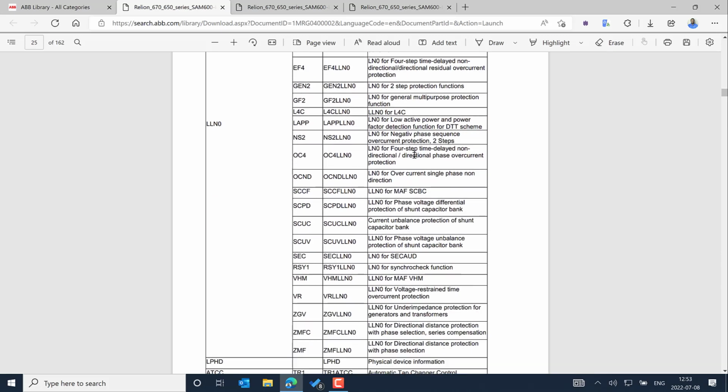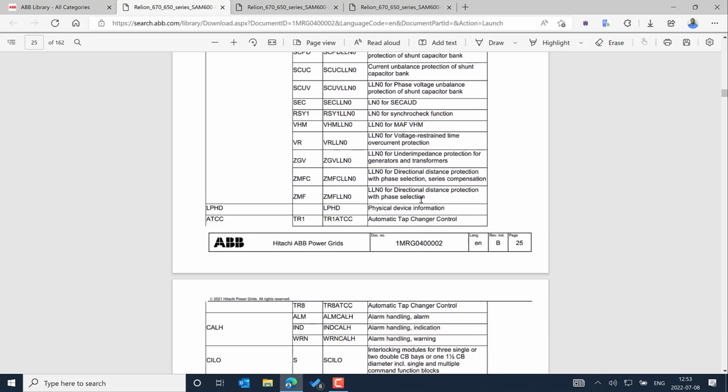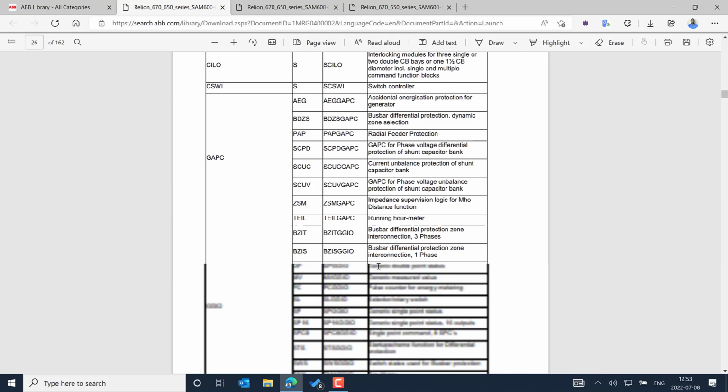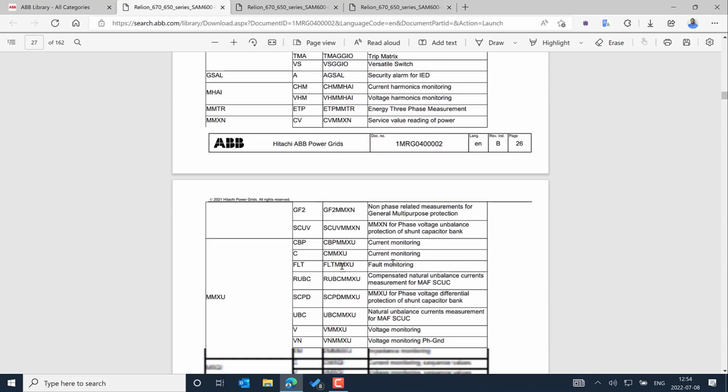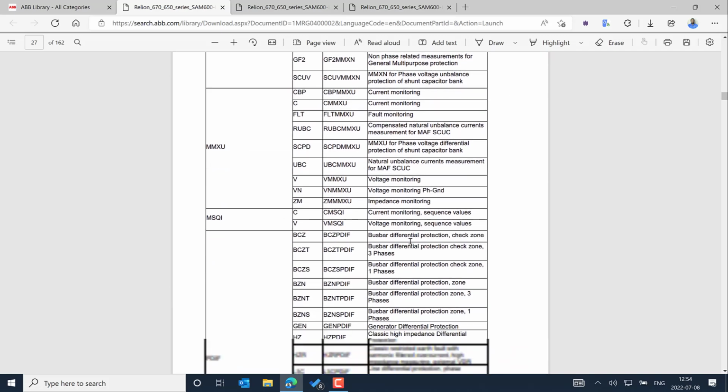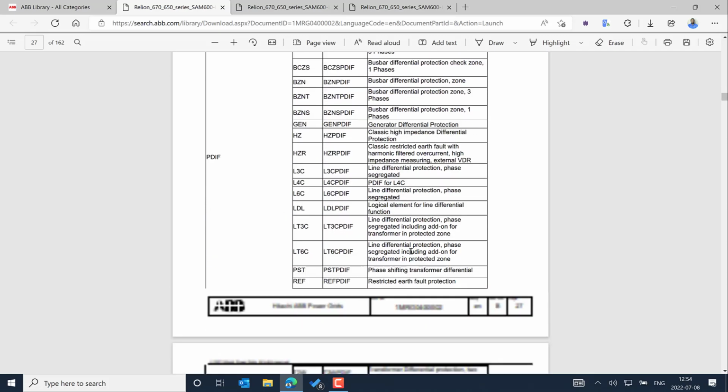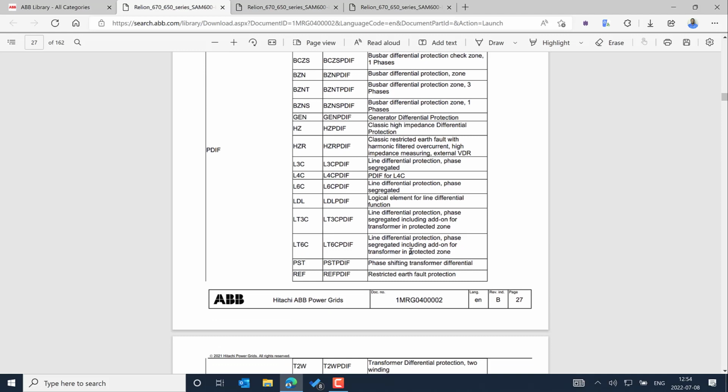So the description comes from the SCL file, and sometimes some of the descriptions are not clear. So in that case, you can refer to the model implementation conformance statement. There you can see the signal in detail. So the attribute or the particular parameter functionality in order to map the right data attribute to the different services like RCB, GCB requirement.